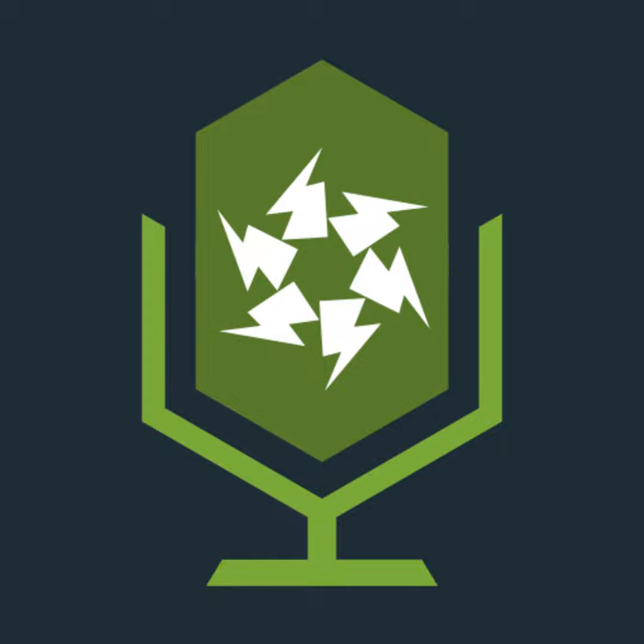Without going into too much detail with it, the purpose of the 0.8 factor that we have given here under Zs(m), and it does say the symbol Zs(m) is the measured impedance at the most distant point of the relevant circuit. The reason we have this 0.8 factor is a general rule of thumb to consider the temperature variation. When we install a new circuit or we commission a circuit, it's not under load. It's not under considerable temperature change. It's maybe installed in a wiring system surrounded by other conductors that, again, are not yet put into service.